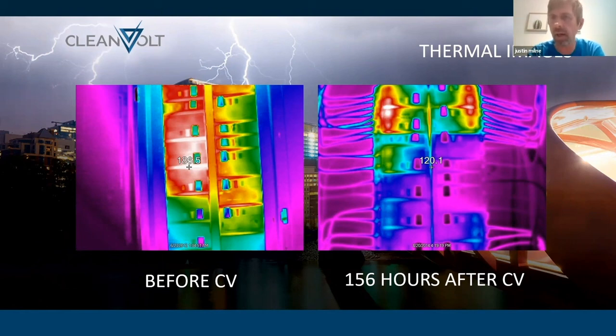It was a ventilation panel, so there are VFDs associated with these fans. And as you can see, that's why there's still heat signatures left on the panel. There's most likely micro fractures that have happened on the bus and behind the breakers, caused by all the energy surges and the heat throughout the years. And we recommended to the customer that they pull their bus out, replace the bus, and even replace any breakers that have been subjected to this heat for anything longer than a year. So this stuff's pretty interesting too, and another benefit you can keep in mind, depending on whether or not you experience that sort of issue in your facility.